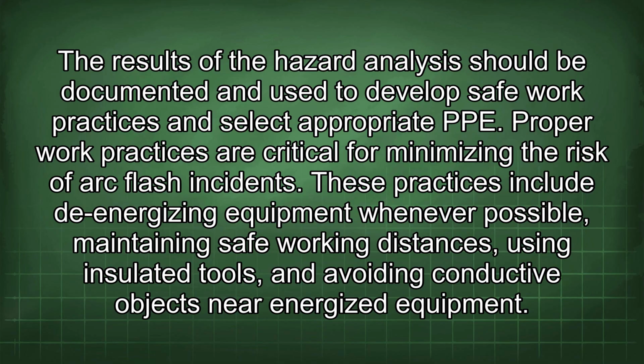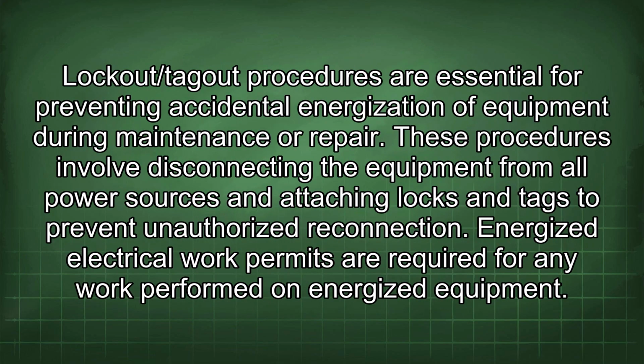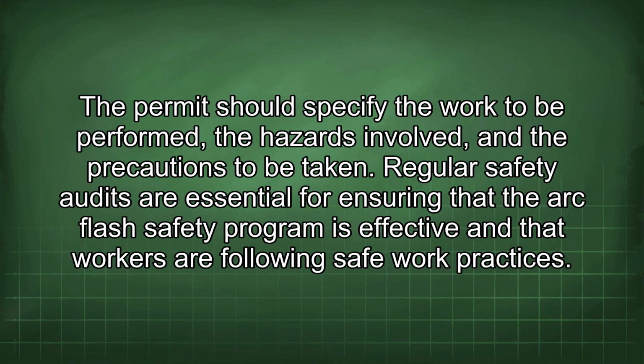Proper work practices are critical for minimizing the risk of arc flash incidents. These practices include de-energizing equipment whenever possible, maintaining safe working distances, using insulated tools, and avoiding conductive objects near energized equipment. Lockout/tagout procedures are essential for preventing accidental energization of equipment during maintenance or repair. These procedures involve disconnecting the equipment from all power sources and attaching locks and tags to prevent unauthorized reconnection. Energized electrical work permits are required for any work performed on energized equipment. The permit should specify the work to be performed, the hazards involved, and the precautions to be taken.